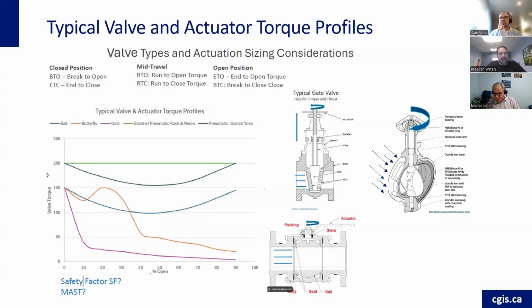Right. Okay. Hey, Martin, just for my own understanding, can you give a quick explanation of the electric and pneumatic rack and pinion versus the pneumatic Scotch yoke lines there, and why they're different? Yeah. So the electric actuator and the rack and pinion pneumatic actuator are capable of outputting a consistent torque depending on demand, based on the resistance that it's encountering. The Scotch yoke is a little bit different. It has a parabola, or a unique curve, because of the construction, the piston itself acting on the yoke of the actuator. There is a slip fit on that. I have to show you a picture. We can get into that.